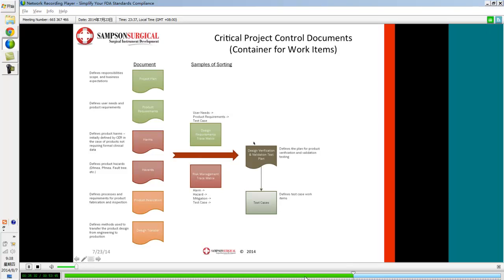other kinds of information. So a harms document, as an example, you might want all kinds of information in there, from field reports, and maybe have a clinician sign off on the harms document. So in the end, you have a document that really ties out the harms, and you have somebody checking on the severities to be sure that it's justifiable that you're putting a 3 instead of a 5 on some particular harm.